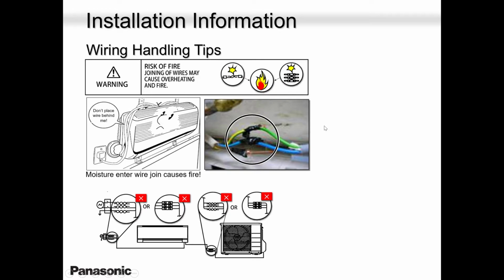Another major problem with our heat pump and our communication technology: joining wires is not required. We don't want you to join wires. You will have problems. Please do not join any wires. Line 1, line 2, number 1, number 2, number 3, communication line, please do not join these wires. You will be called every week. If not every week, you will be called once every 2 weeks. You will have to reset the power and go forth because you joined this wire. They are causing some kind of communication resistance here, causing the unit to trip on H11.